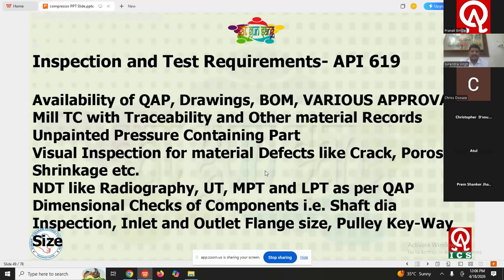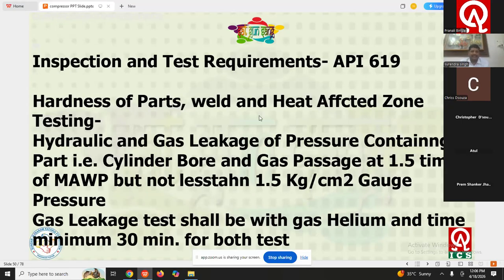Again, visual inspection, you have to check the defects on castings for crack, porosity, shrinkage, NDT, radiography, UT, MPT, and LPT. As per QAP, you have to witness. Again, dimensional check of components for the shaft diameter, inlet and outlet sizes, pulley, keyway, etc. You have to check. Same for hardness of parts, welds; you have to check at parent metals, welds, and the heat affected zones, hydraulic and gas leakage of pressure containing part.